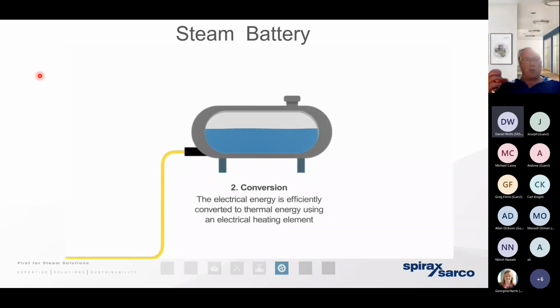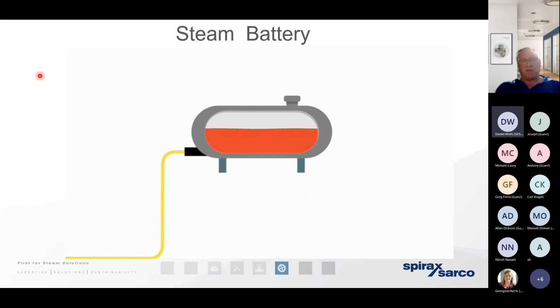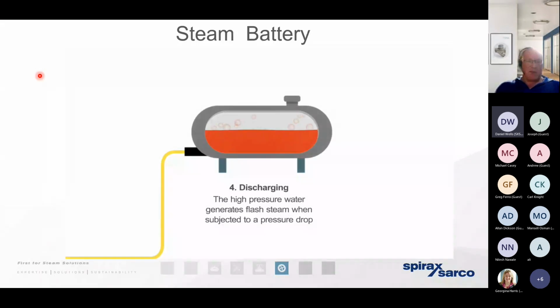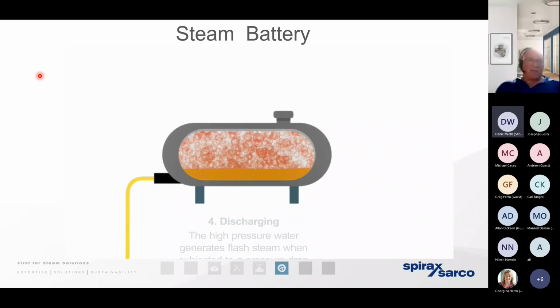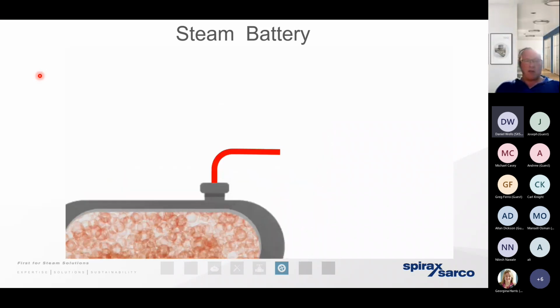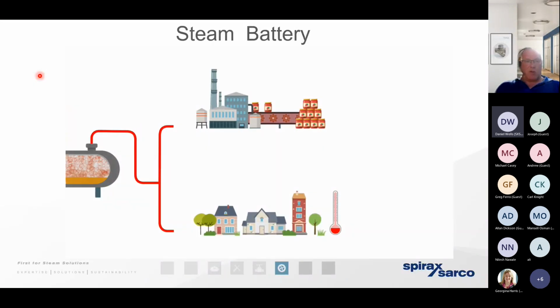But whilst that renewable energy is available, it will use 100% of it and store it thermally in the form of charged hot water until such a time that the process requires that thermal energy. Steam at the end of the day. The process doesn't care how that steam's going to be generated. It's basic physics. We're depressurizing hot water to produce that thermal energy.